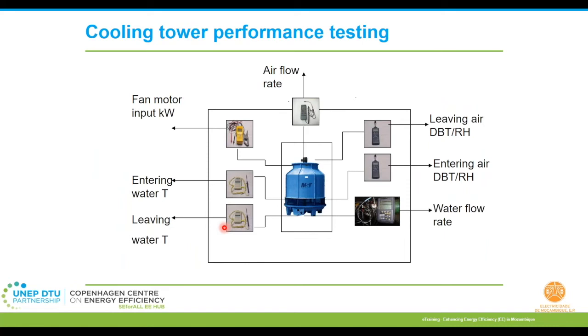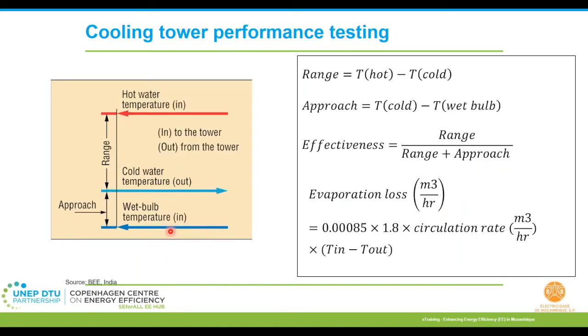Moving to the cooling tower performance testing, these are the different parameters that I'll be needing to evaluate the performance of the cooling tower. And these are the different formulas. So basically I'll be trying to measure what is the range, what is the approach, what is the effectiveness. These three indicators, I would say, can give you an actual indication about how your cooling tower is performing. You can also evaluate up to what extent you are losing water in terms of evaporation through the cooling tower.